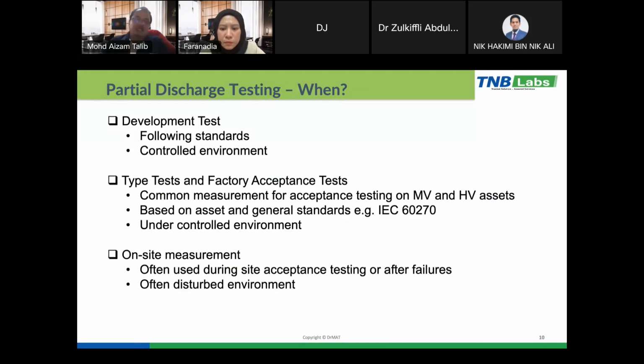So when we need to do the partial discharge testing, there are different stages where we require the partial discharge testing. The first one is during the development of the test, so that we can simulate the function of the design of the equipment. The second one, we need to do the partial discharge testing during the type test of the equipment or the test object, for example, transformer, cable, switchgear, and also during the factory acceptance test.